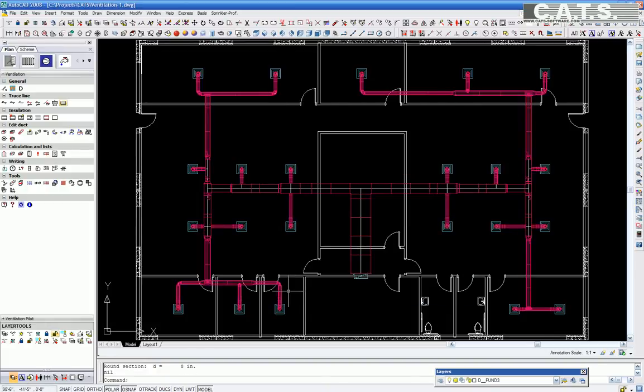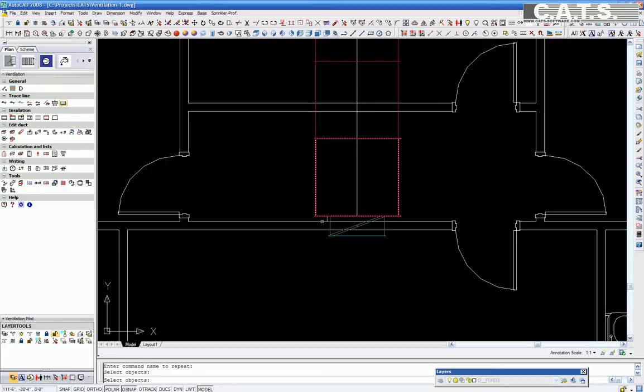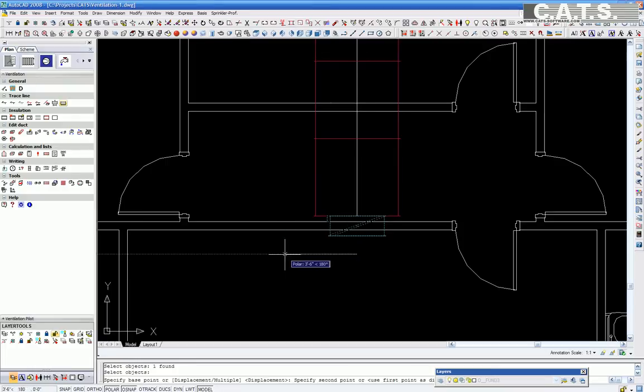The duct size, width, is now created. And we have previously selected our duct height. We will now copy the fire damper. Relocate five feet to the left to create our return air duct penetration.